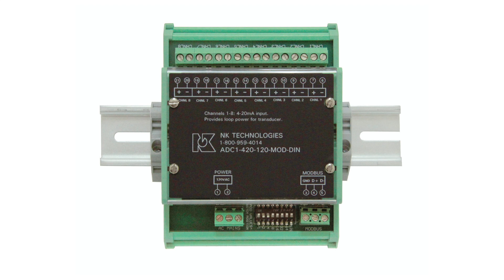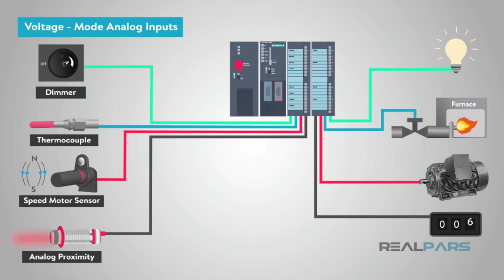Now the output signal types. The first output signal type is the analog output. These analog outputs provide a continuous signal which is often in the form of a current ranging from 4 to 20 milliampere or a voltage ranging from 0 to 10 volt, which is proportional to the measured variable. For instance, a temperature sensor might output a range of signals corresponding to different temperature levels.